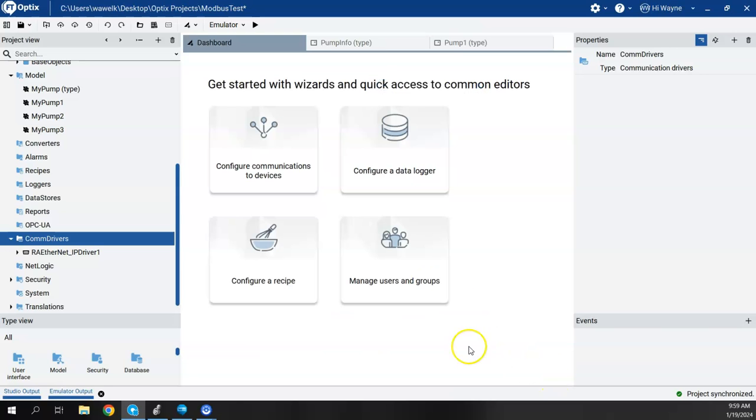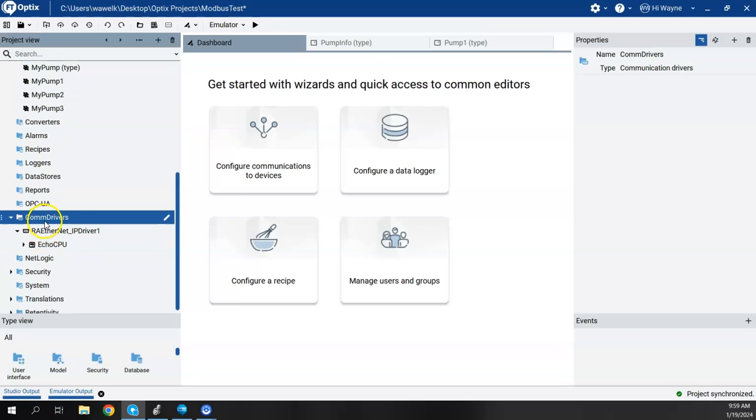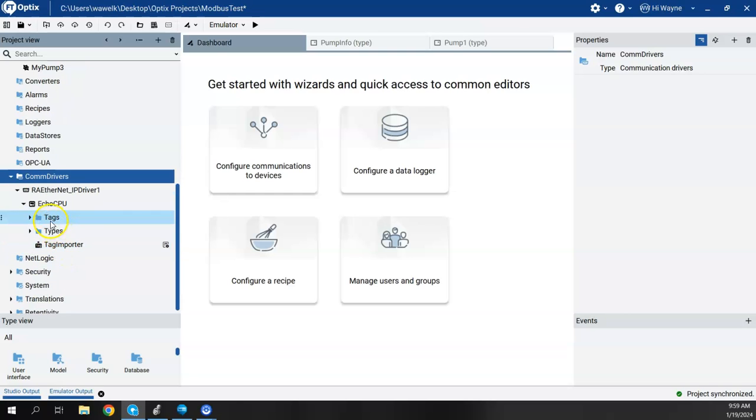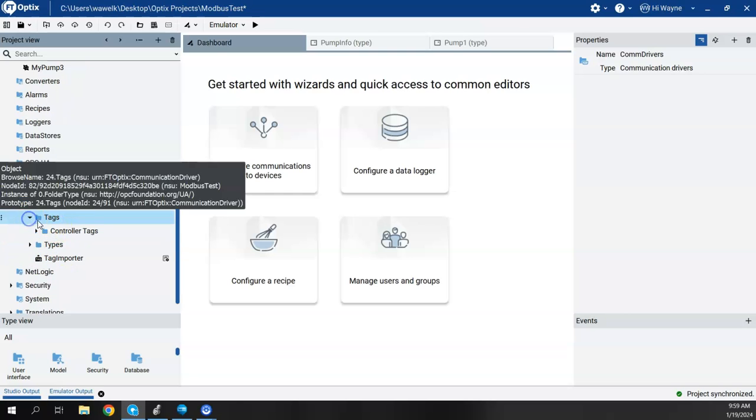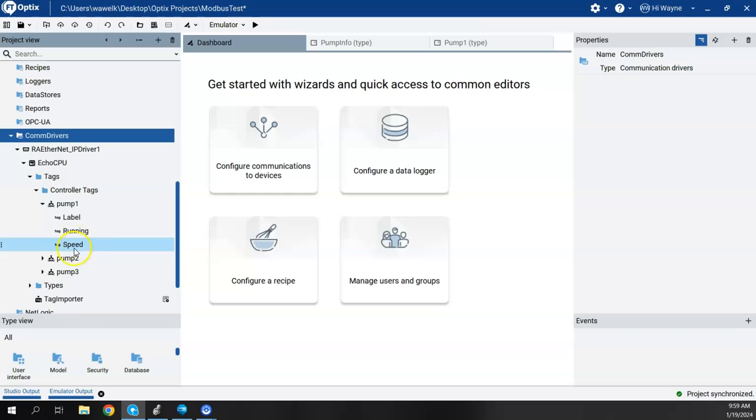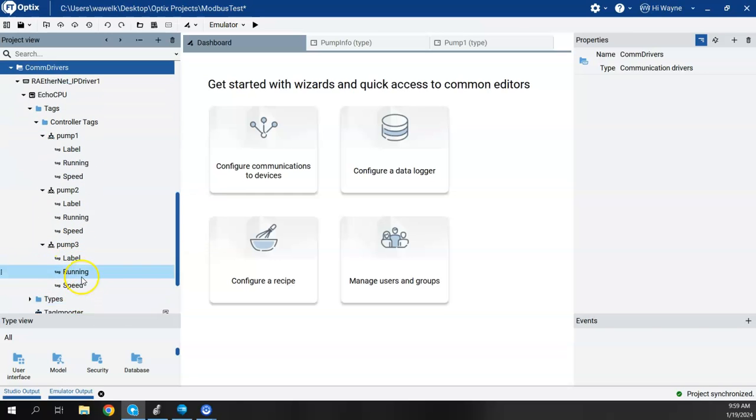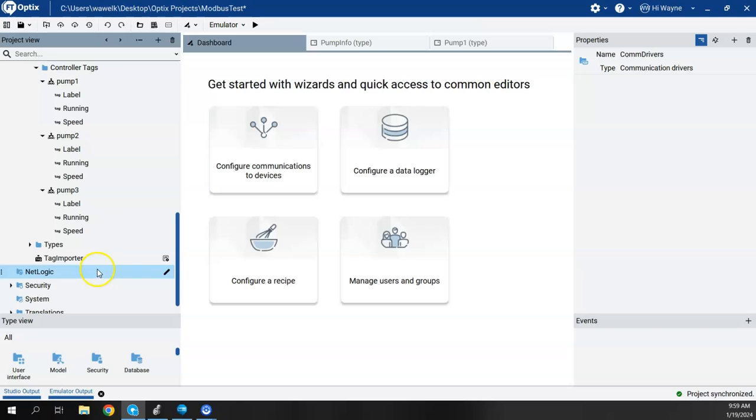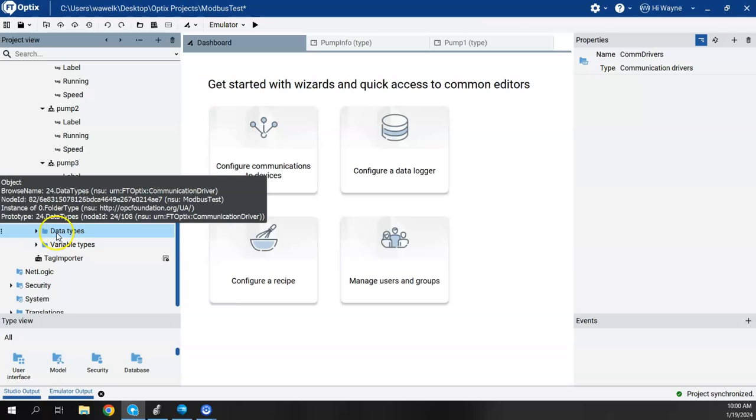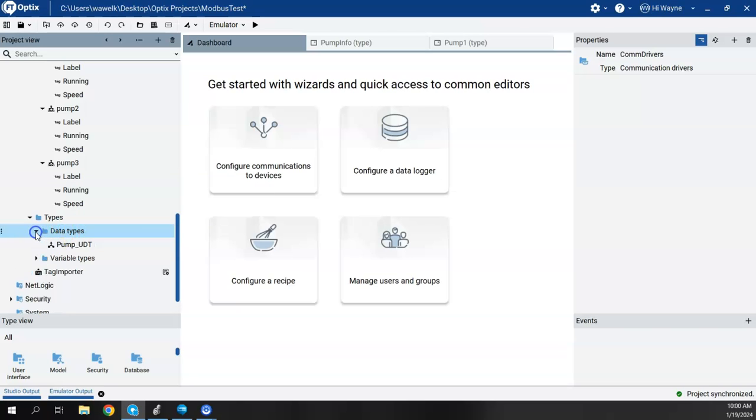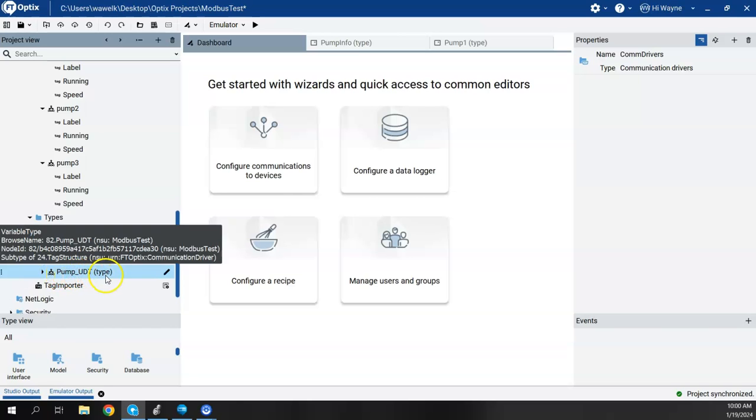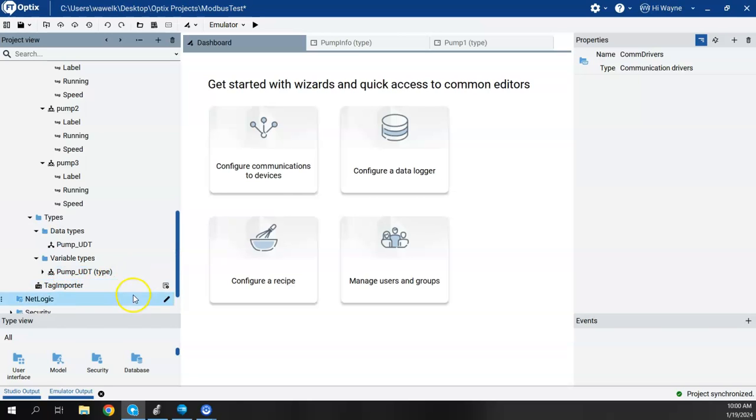So we say Exit. So what I want to show is now that we've imported our tags, we now have the Echo CPU. And then under the tags, controller tags, there's Pump 1, 2, and 3. So there's Label Running Speed, Label Running Speed, Label Running Speed. But if I come to Types, also underneath that Echo CPU, I see Data Types, Pump UDT, and Variable Types, Pump UDT. And it is actually a type already.